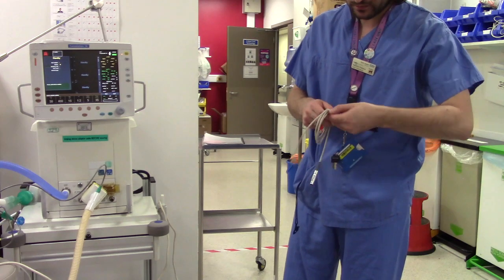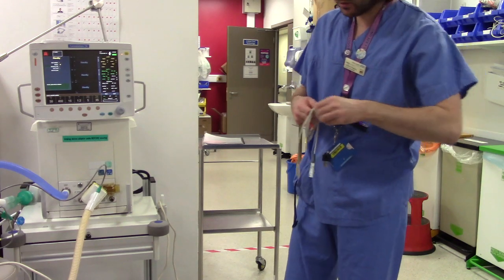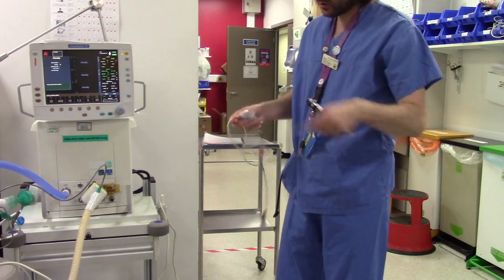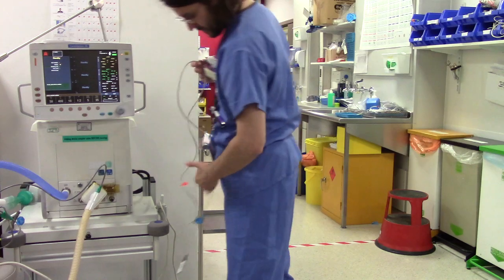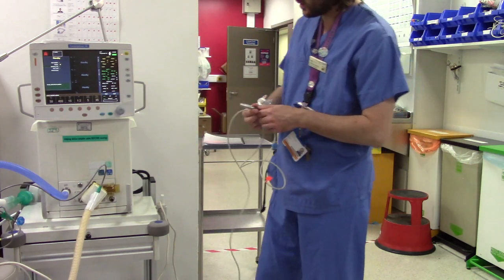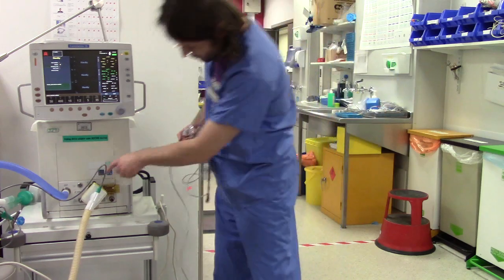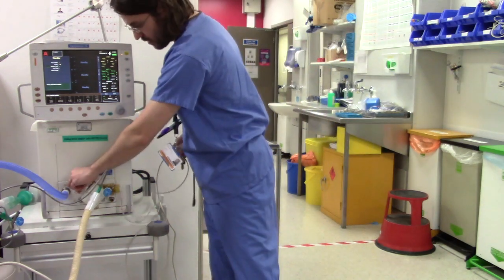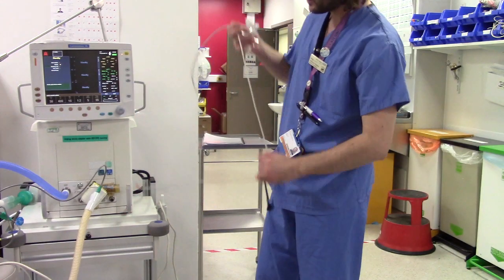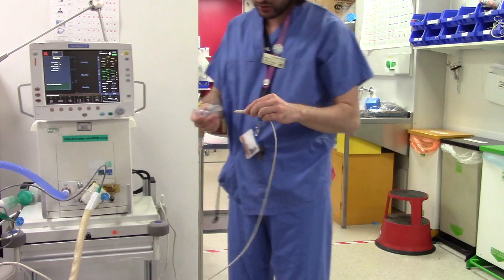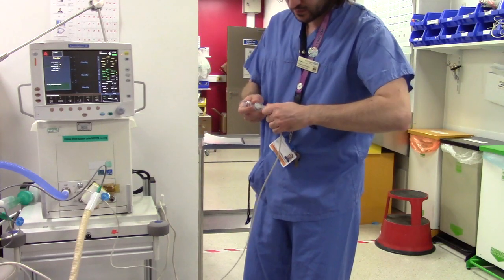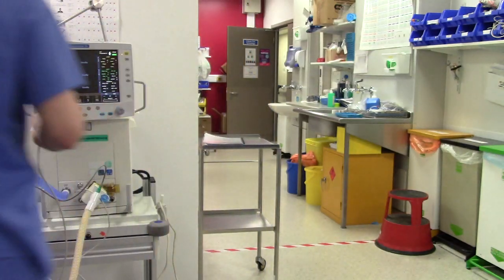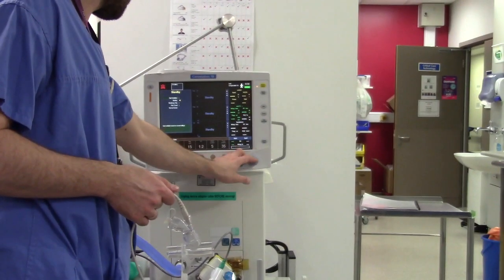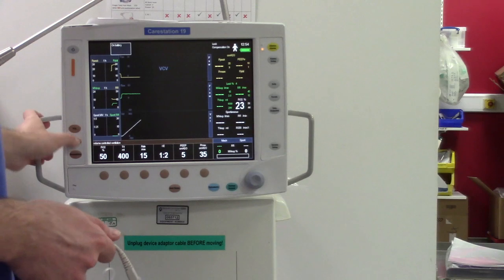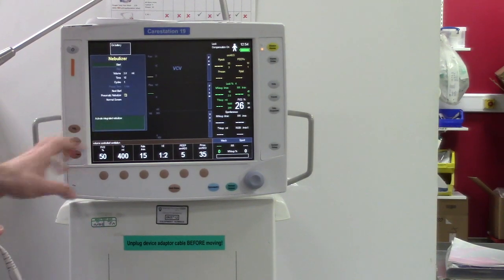You'll find it in our storeroom, and you need this cable. You connect the cable to this port over there, and make sure you connect a red dot to the red dot. Otherwise you may break the port. So it's connected, and then you connect it over here. Now you need to tell the ventilator to start it. We'll have to start the ventilation first, and then you go to the nebulizer.